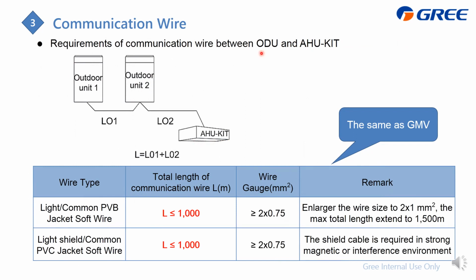Next is for the communication wire, which is from the AHU kit to the outdoor unit. And for this part is the same as the GMV requirement, which is we can make it to be max 1 kilometer. And if you enlarge the size of the communication wire, you can make it to 1.5 kilometer.